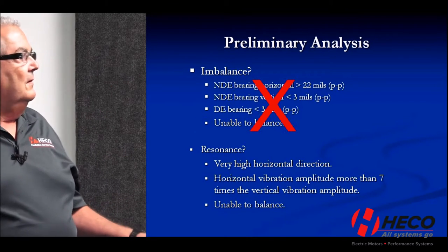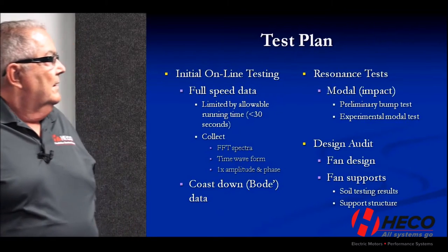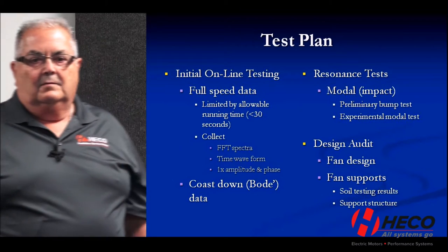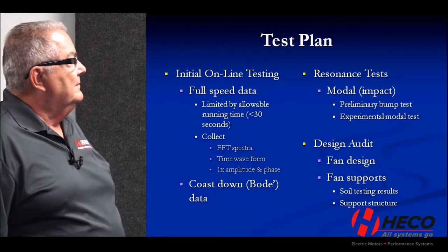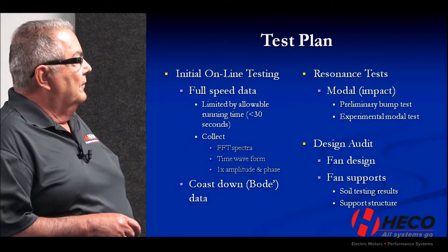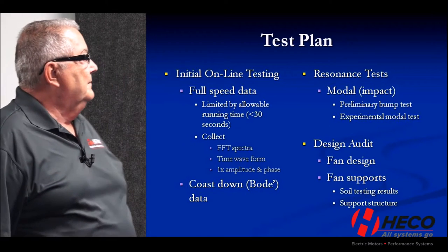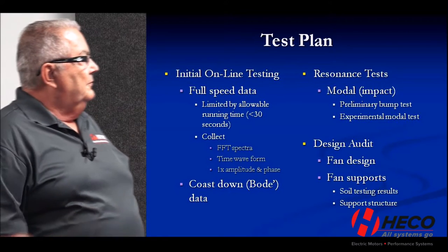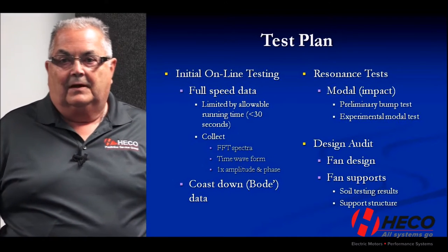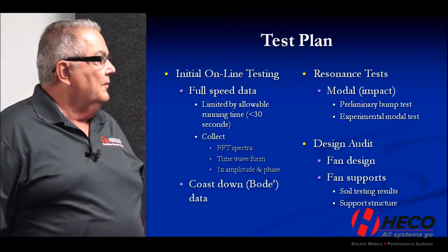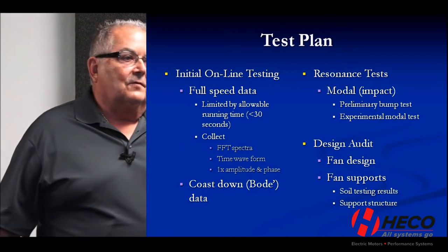Looking at his data, I didn't think we were looking at a pure imbalance situation. So we developed a test plan to acquire data and prove one or more of these hypotheses. I wanted to get full-speed data on all bearing locations — start it up, run it, and collect everything. However, the tech rep said we're not going to run this fan for more than 30 seconds because it's too violent and will take out the bearings. So we had a 30-second time limit to collect data.